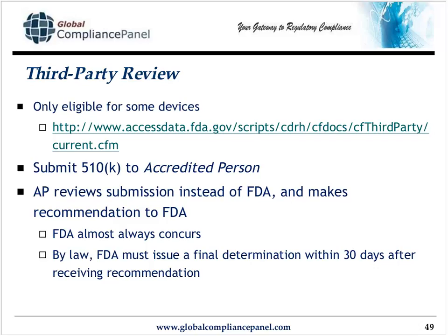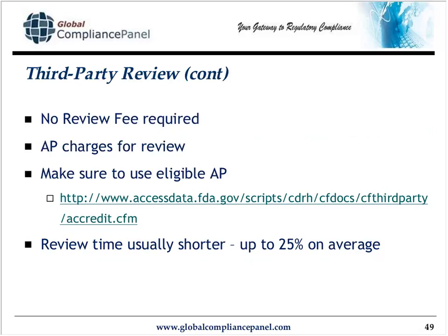The FDA almost always concurs, and by almost always, I mean every situation I can recall in which I've either used a third party or people I work with in the industry have used third parties. Every situation I can recall, the agency has always concurred with the recommendation of the accredited person. By law, the agency has 30 days after receiving the recommendation. I don't know what you would do to them, but by law, they have 30 days. Like I said earlier, you don't have to pay for the 510K review, but you do have to pay the accredited person or company for their review.